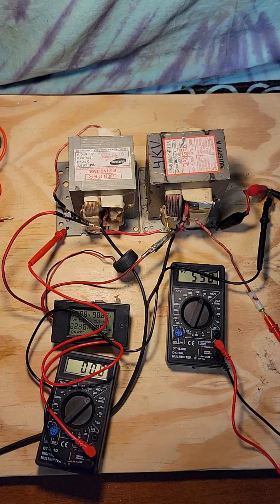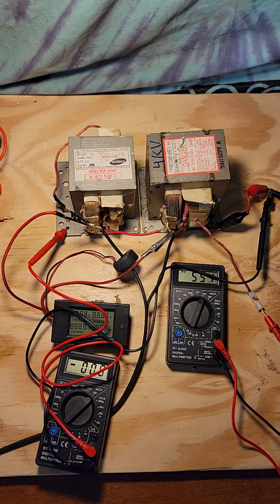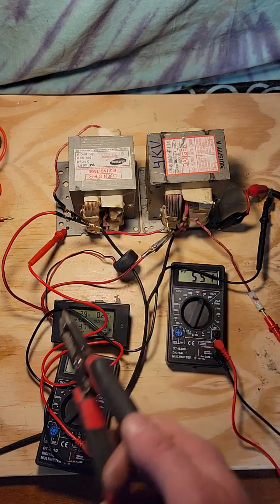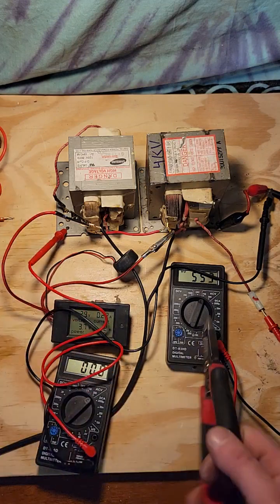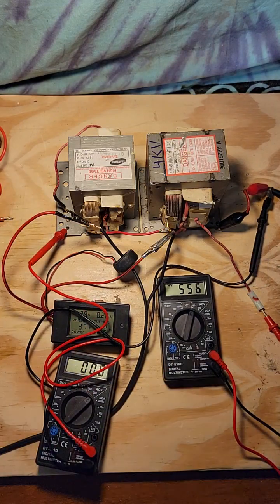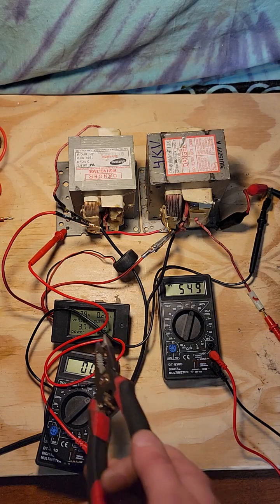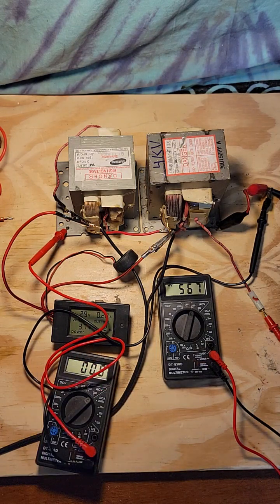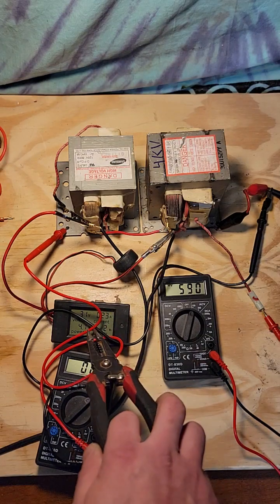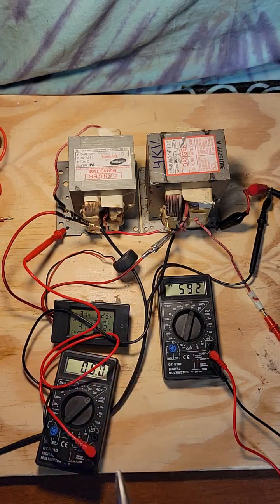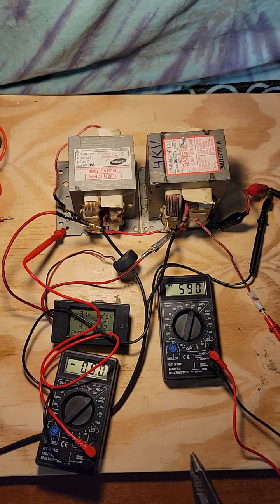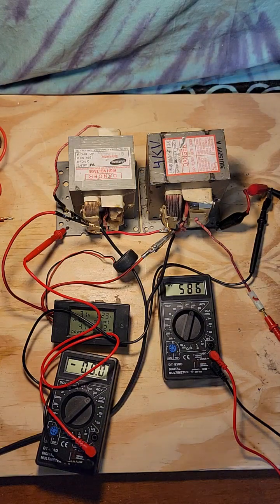So, still no voltage potential between the two cores, even though they're not connected in the center. But with that grounded, you get 600 volts from 30 volts. So yeah, it's still about 2500, and probably drawing about an amp on the primary side. So the current is far less too.